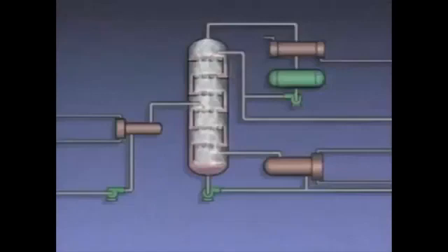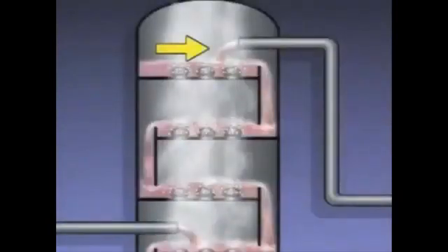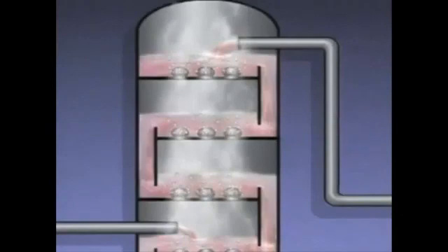While excessive liquid flow from a higher than normal feed rate is one cause of flooding, there are other causes. For example, a higher than normal reflux rate can have the same basic effect. Reflux is condensed overhead product that's pumped back to the top of a column. If there's too much reflux, the level of liquid on the trays can rise, increasing the hydrostatic pressure of the liquid and restricting or blocking the rising vapor.